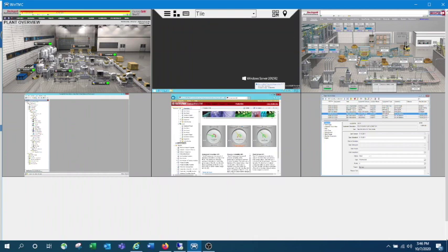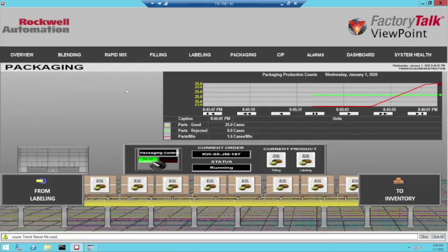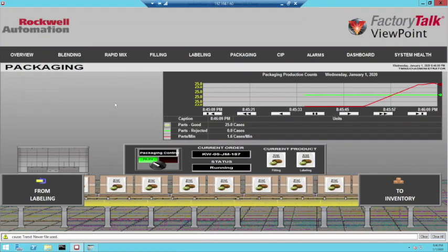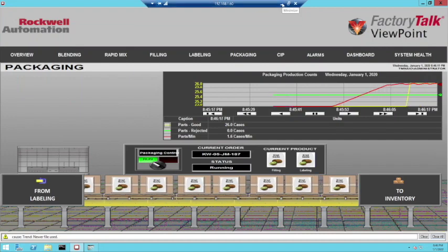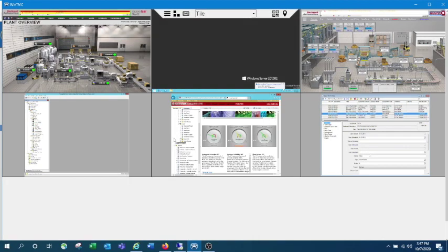So I like to demonstrate having both of these up, so that way in the event of a failure, the Thin Manager would failover, and also my HMI would wireframe. So right now I'm going to pull the P1 cable on node 1, and we're going to simulate a failure. So right now I'm going back. From the operator standpoint, nothing's changed, everything looks good.